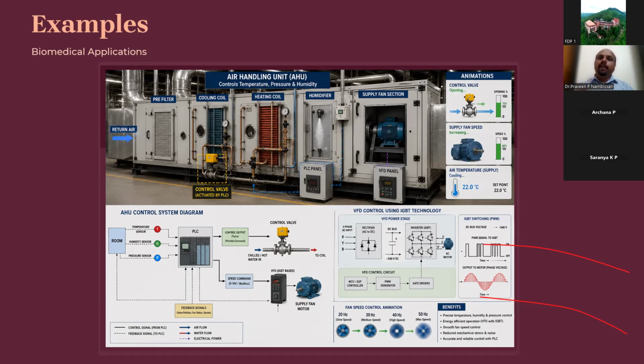Normally it runs at 50 Hertz, as we know. So I reduce the frequency to 45. What will happen? The current through the phases will be reduced. If the current is reduced, the power output normally gets reduced and the energy consumption will be reduced.